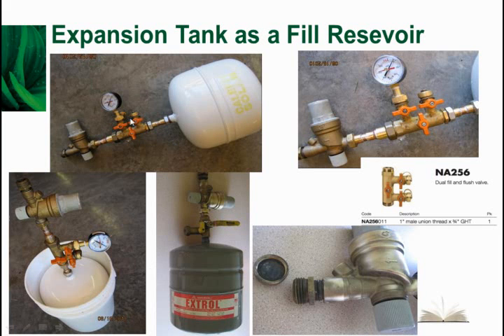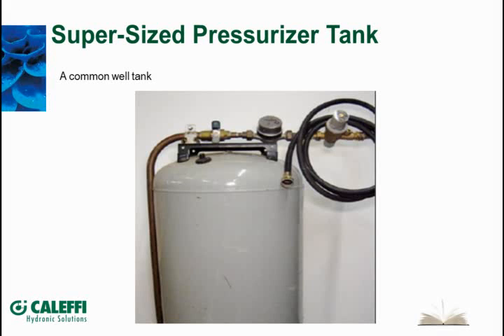Another little valve you can do if you don't want to use one of these fill purge valves, you can just get one of these little 3-port valves that are on the market now. They've got a little side connection with a hose connection there and a little shutoff valve there. So you just pump this up to, you can pump about 100 pounds in these. I think these things are rated right down here on the sticker at 150 PSI. So pump up to about 100, 125 pounds. Now you've got glycol in there or fluid in there, and then your fill valve will regulate the pressure going into your system. Little cap on the end so none of the fluid will drip out as you go on your way out. And of course, you can supersize that depending on how much water or how much fluid you want to take along to the job with you.